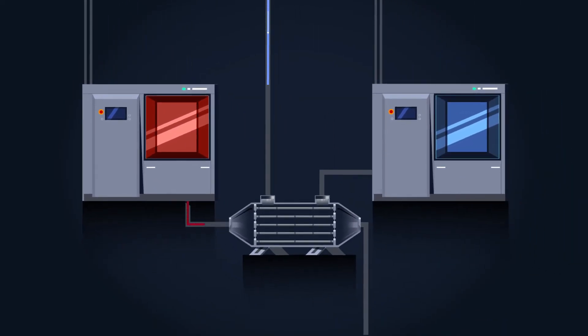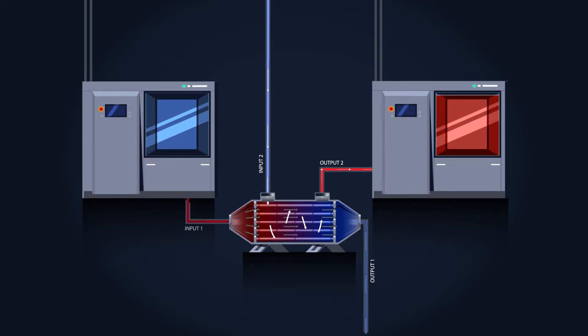Instead of releasing the heated cleaning water to the drainage after the process, the heat energy could be used to heat up the water for the next batch or another machine.